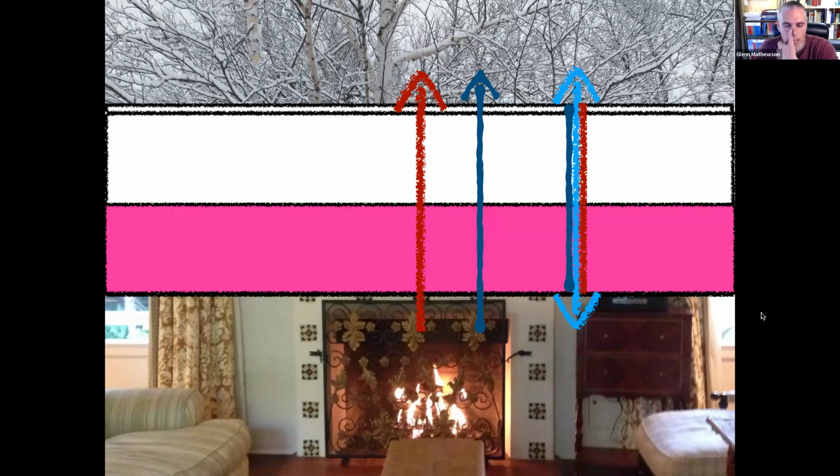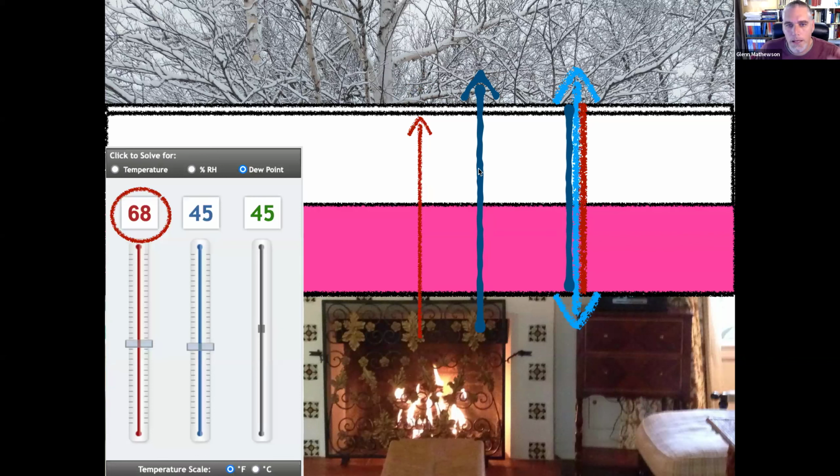So what happens, right? We come and we throw in this line of insulation across there, and the goal is to reduce the amount of heat loss. We paid for it and we want it for our comfort. That's what we're focused on. So we insulate and we reduce the heat. Now, what did that mean? The warm, humid air that's in this attic space hits and touches the solid surface of that roof sheathing. Well, theoretically, we've lowered the temperature of that air, right? It's not 68 degrees inside, but we're slowing how much that heat can move into this cavity. So we assume we lower the air temperature a little bit, of course.